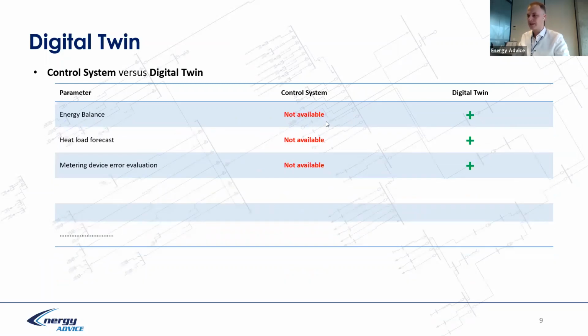Energy balance automatically every 5 minutes is probably not available, because the water side yes, but the flue gas side or fuel side no. Heat load forecast probably no. Metering device error evaluation probably no. However, a digital twin can. And we can put here a lot of other points or data which are blind spots, what we cannot measure, or where we should control the error of a measurement.